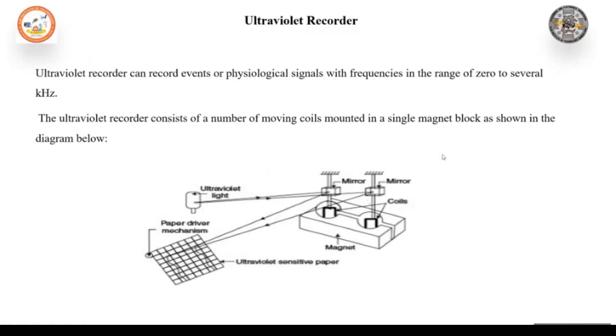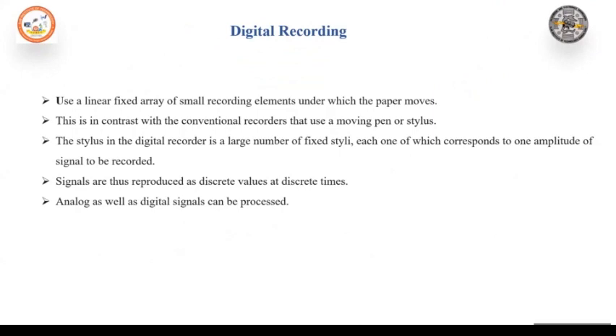The ultraviolet recorder consists of a number of moving coils mounted in a single magnet block, and it is shown in the diagram. So next, coming to digital recording. It uses a linear fixed array of small recording elements under which the paper moves, and this is in contrast with the conventional recorders that use a moving pen or stylus.